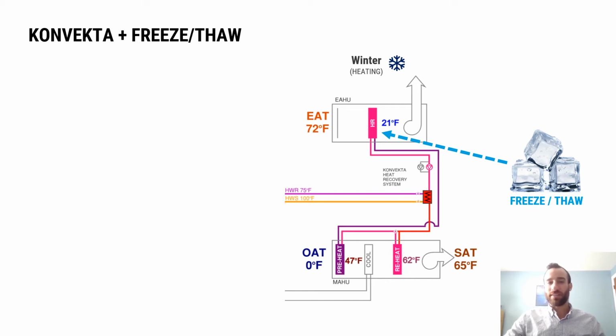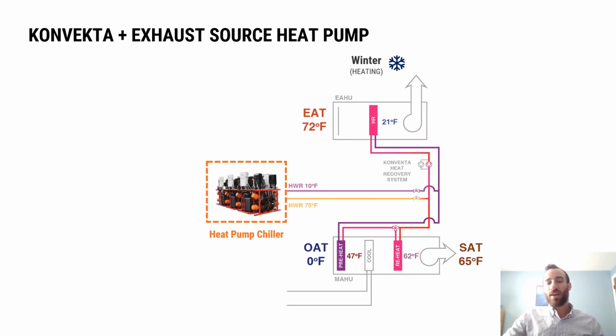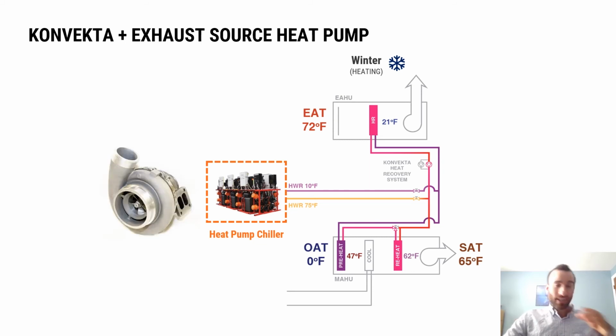So that's something that KONVEKTA is now doing, which is really exciting, to intentionally freeze those coils. And that opens up the potential for us to throw a heat pump chiller into the mix here. We can purposely cool the fluid going to the exhaust airstream even further. And the more we cool the exhaust, the more we heat the supply. So in this application, we're able to get 65 degrees off of our air handling units at 0 degrees ambient without using any fossil fuels to do that heating. So I liken this to having a turbocharger in the system.